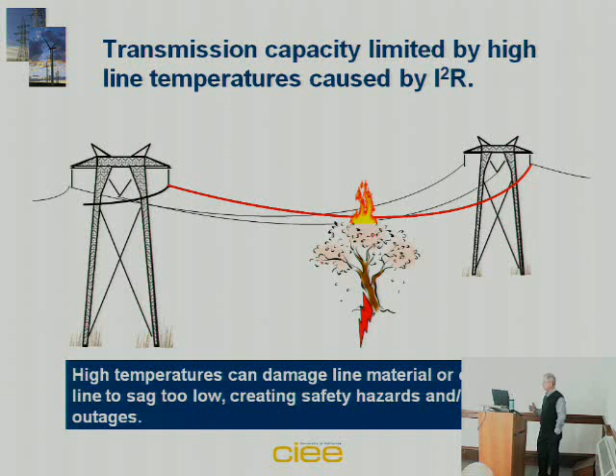The transmission capacity is also limited by local instabilities. For example, looking at the LA basin, which is probably going to turn out to be the poster child for problems in California. One study done by CITRIS and EPG, the Electric Power Group, who happen to live in the LA area, found that two-thirds of the renewable generation will likely require delivery to the transmission gateways surrounding the Los Angeles basin. This is fundamentally the fact there's load there, and Kirchhoff's law is going to direct most of that generation out in the deserts there and the Tehachapis to the Los Angeles basin. The capacity is limited by voltage and transient instabilities as well as thermal limits.